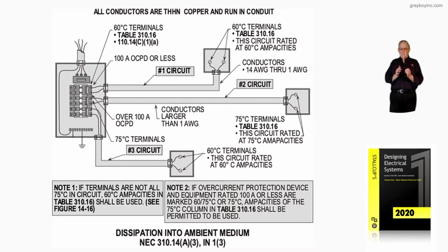334.80 in the NEC. It's so simply identified there and outlined that even I think a child could understand it reading it. It's that clear. So read that so that you get a good feel that I can take a 90-degree conductor as a designer or installer and use that 90 degree to derate back to a usable 60 or 75. Now that is fully illustrated to us in 110.14(C), as well as 334.80 in the NEC.